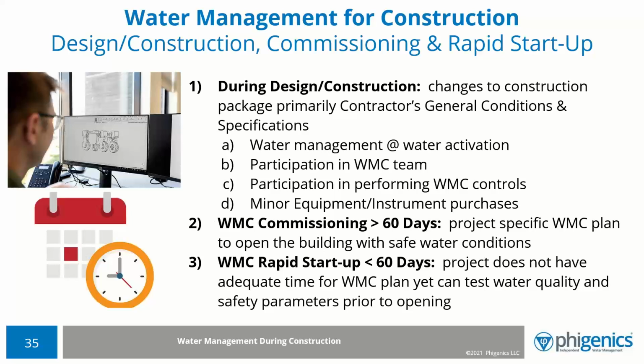The other thing on the commissioning side of it that I've talked about—although the standard talks about this 3-week window up to beneficial occupancy, we find that you really need 60 days. So projects that are 60 days or greater, you could have a formal commissioning process.